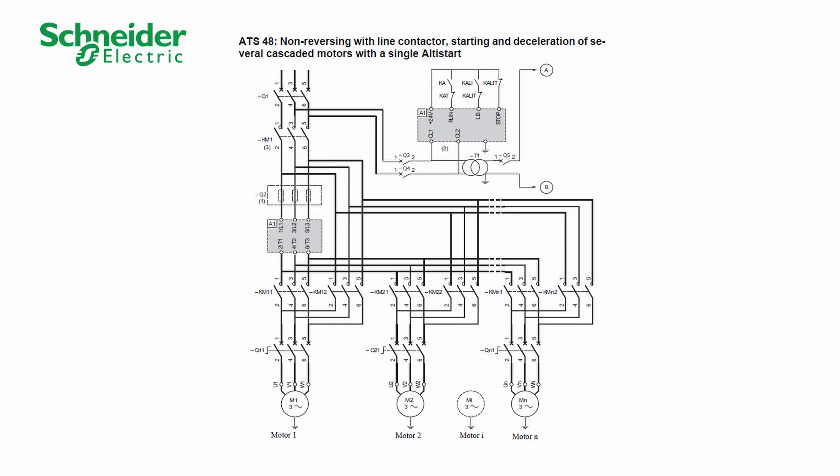Now we start the motor by closing KM1, KM11 and Q11 for the main supply, followed by KA for the Run command. The motor M1 starts following the parameters of the soft starter.